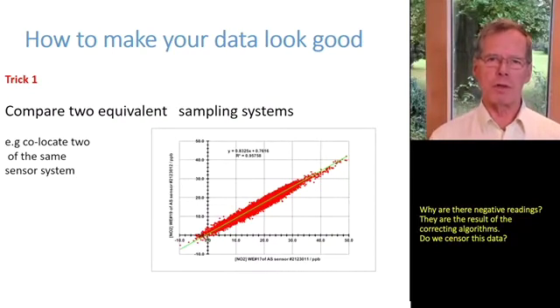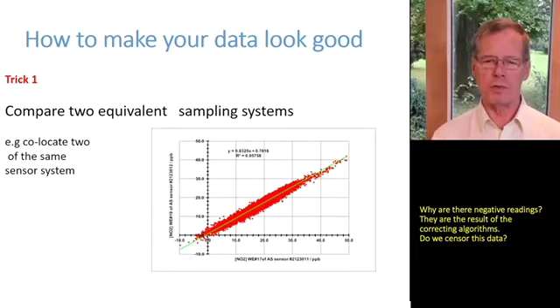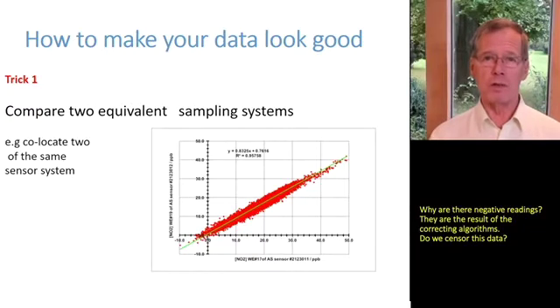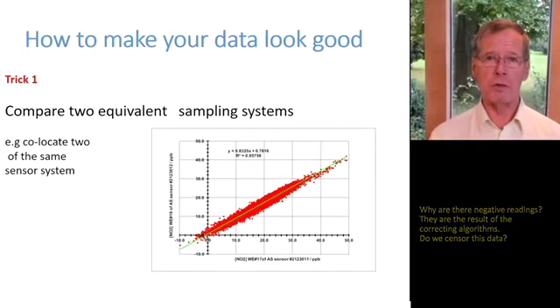Let's now have a look at how we can make our data look better and how some people make their data look worse. Making your data look better — trick number one: compare on the x and y axes equivalent sampling systems. Here, for example, there's data of electrochemical NO2 sensors, both effectively the same sensor technology measuring co-located in the same time and the same location. And you get an incredibly good R-squared of 0.95. That shows that the sensors are repeatable with each other, but it doesn't show the true quality of the data relative to a reference system.